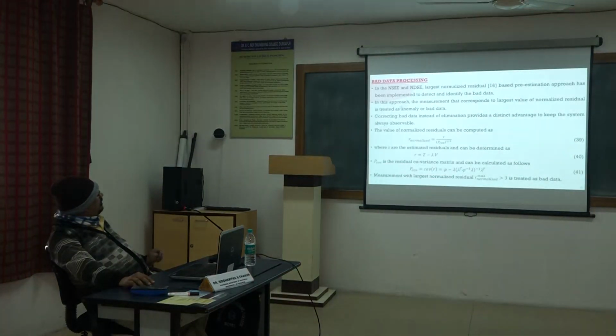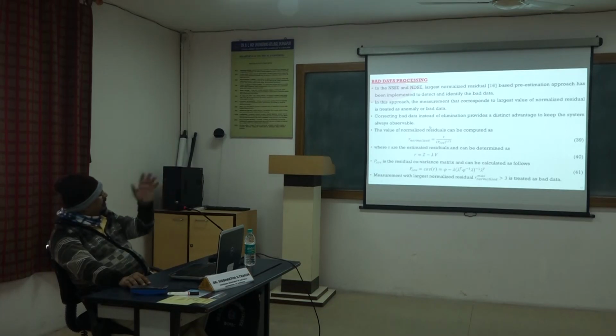For bad data processing, we use a pre-estimation technique. That is, before the estimation takes place, we detect and identify the bad data. In this approach, the measurement that corresponds to the largest normalized residual is treated as anomaly or bad data. Now, as I said, correcting bad data instead of eliminating it provides a distinct advantage: it keeps the system always observable. The normal procedure is to detect, identify and eliminate the bad data, but that can make the system unobservable. Correction of bad data always keeps the system observable.